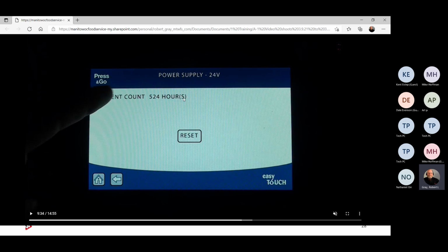However, let's say I was out on a service call and I go in to update my tracking, or I want to confirm that it wasn't changed before, to make sure I'm not missing something. I'll go into advanced, take a look at it. It's like, oh crap, somebody just replaced that yesterday because I only have 10 hours of use on it. So my troubleshooting procedure was wrong, or whatever the case may be. I'm going to go back and double check my diagnostics because somebody replaced it the day before or 10 hours ago, and I'm a different technician. Or even if I was the same technician, I don't want to replace it again and still have the same problem reoccur.